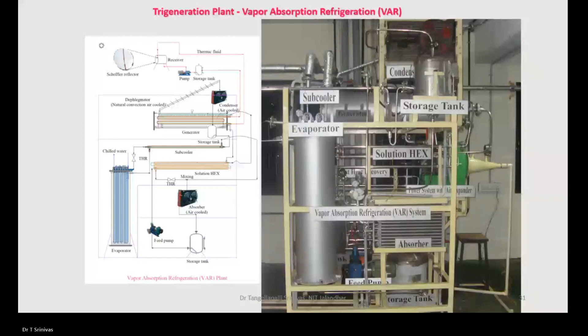Yeah, this is the heat pump based poly generation system. This heat pump based poly generation system is redesigned into a vertical model. Because in earlier slides, you see mostly the horizontal orientation. Horizontal orientation is fine, but it occupies floor space. So once we want a compact design, like a heat pump based compact poly generation system, then all the processes are designed into a vertical duct. This is the vertical heat exchanger.